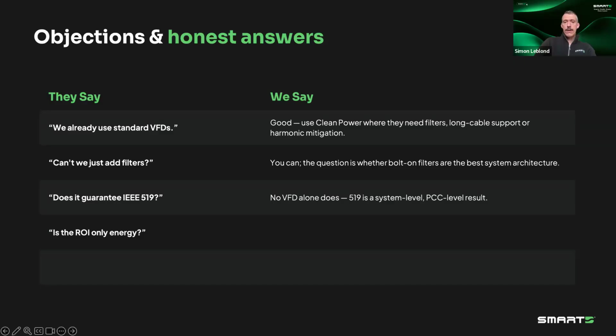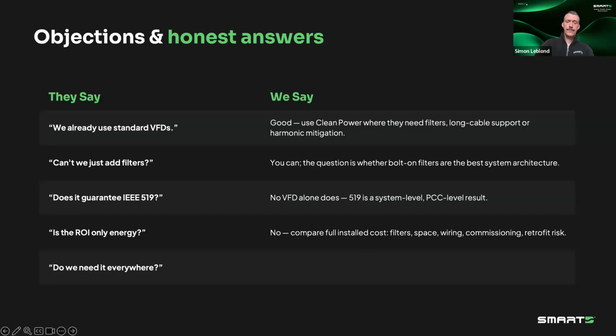So what about the ROI? Is it only energy? Well, of course, the energy saving from a VFD drives a lot of the decision, but in the case of the Clean Power VFD, you need to think about the full install cost, the life cycle cost. So, of course, the filters, the space, but also potential saved downtime coming from that.